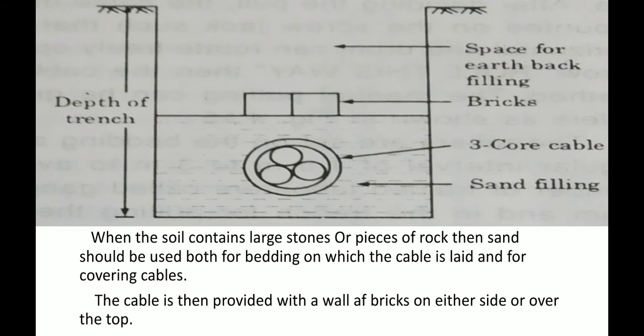The depth of the trench depends on the number of cables and the voltage level. After laying 3 to 4 cables, sand filling is used. The space above is then backfilled with soil. When the soil contains large stones or pieces of rock, sand should be used for bedding and for covering the cable.